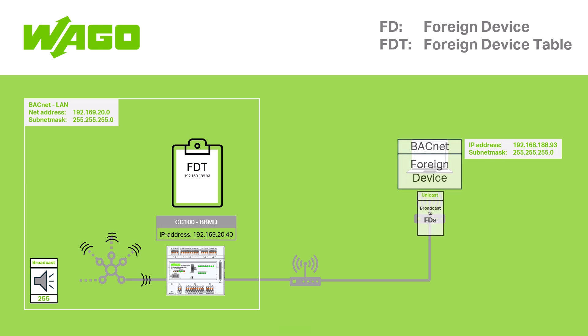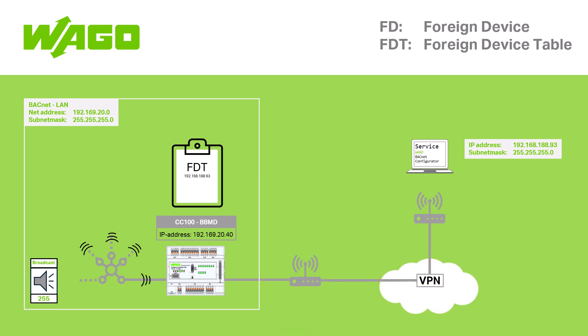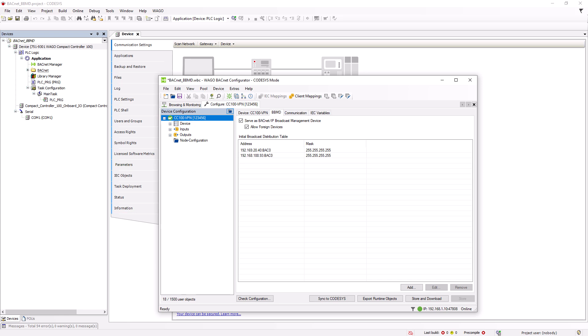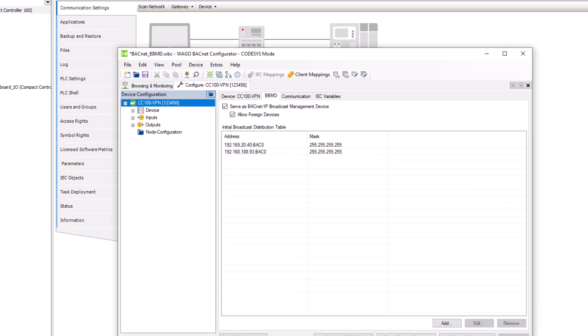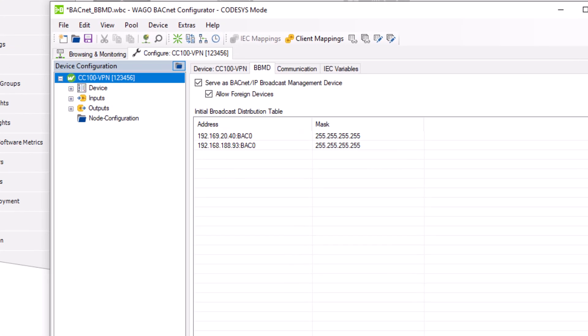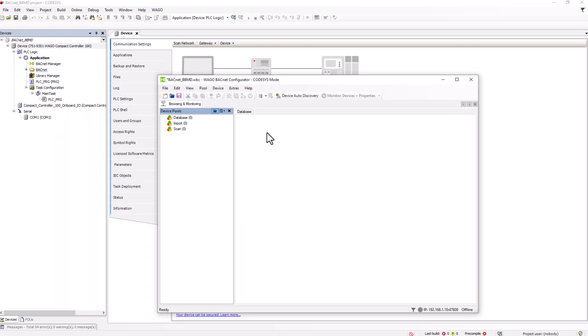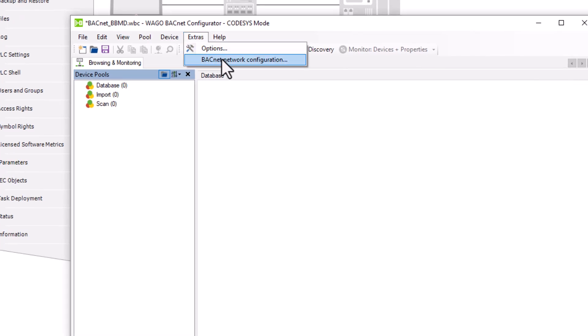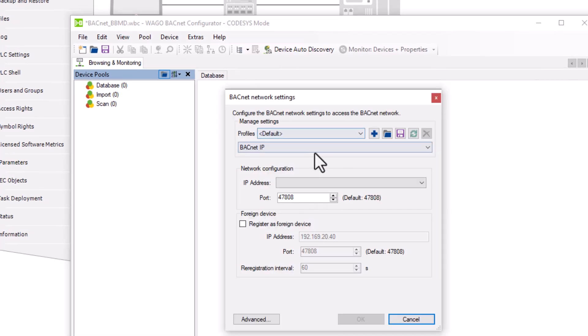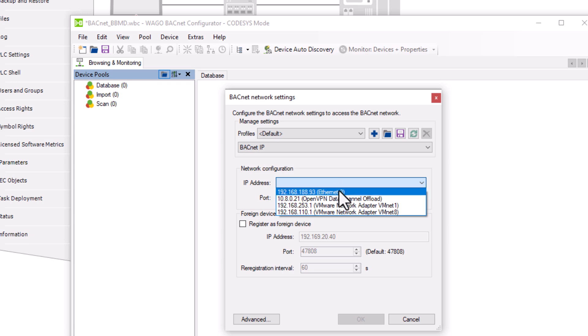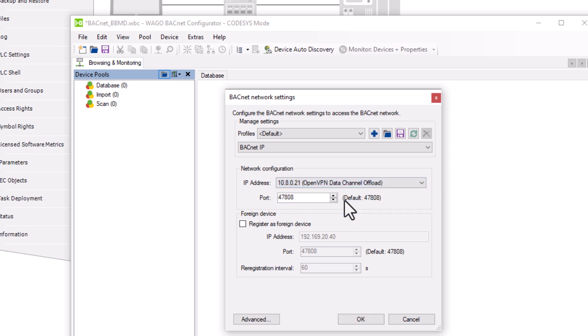A typical practical example is a service PC running the WAGO BACnet configurator, which is to be given access to a BACnet IP subnet in a remote building via a VPN connection. There is already a WAGO controller in the building with the serve as BACnet IP broadcast management device checkbox selected in the configuration. In order for us to be able to register as a foreign device, the allow foreign device checkbox must also be ticked. The VPN connection from the service PC to the BACnet IP network is active and we select the VPN connection as interface in the WAGO BACnet configurator. To register as a foreign device, we tick the register as a foreign device box and enter the BBMD's IP address we want to register with.